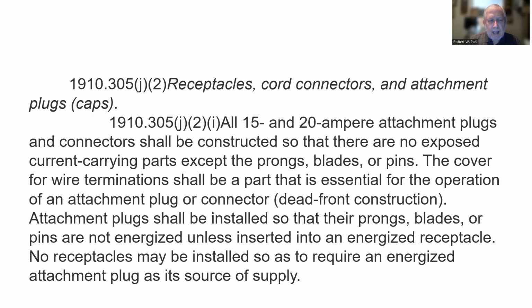Receptacles, cord connectors, and attachment plugs, caps. All 15 and 20 amp attachment plugs and connectors shall be constructed so that there are no exposed current carrying parts except the prongs, blades, or pins. The cover for wire terminations shall be a part that is essential for the operation of an attachment plug or connector, dead front construction. Attachment plugs shall be installed so that their prongs, blades, or pins are not energized unless inserted into an energized receptacle. No receptacles may be installed so as to require an energized attachment plug as its source of supply.